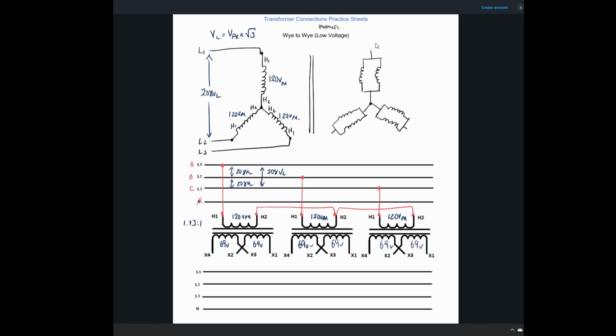So our voltages on the outside, well, let me finish off this guy right here. This guy is going to feed line 1. I had line 2 feeding the primary on the left-hand side, so I'm going to grab line 2 over here, and then line 3 is going to come out and feed this guy right here. Then we do have the center tap right here, and that's going to be our neutral, and that again is usually bonded to ground. Our voltages here were 69 volts on each of these guys. A little bit of dyslexia coming through, sorry, hang on. Beauty, and then we need our labels on the transformer, right? So this one is X1, X2, X3, and X4.